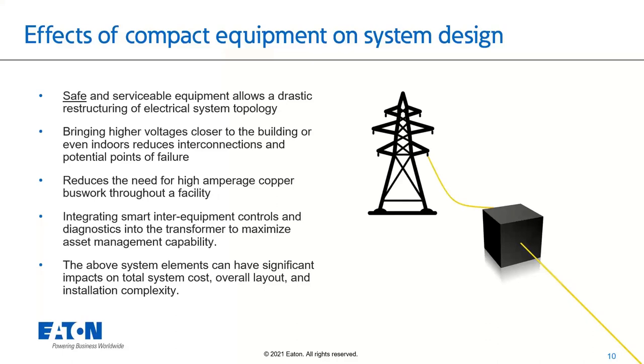And then, of course, the nice benefit that's sort of obvious in eliminating some of those unnecessary components is we're going to get an overall smaller system. Hopefully, that's going to reduce the cost. That's going to reduce the overall layout complexity and ultimately the installation complexity. I mentioned interconnecting, say, an MV switch, current transformers, and relaying, doing all that on site. If we can find a way to consolidate that package into more of a single piece of equipment, that's going to allow us to reduce that headache on site and ultimately make the install time greatly reduced and much less complex.